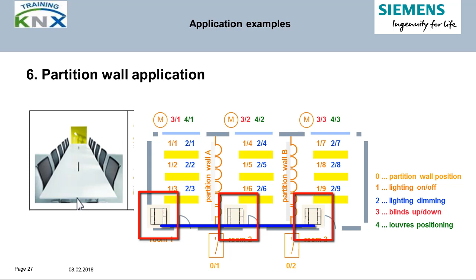The basic requirement is that several smaller, identical rooms shall be combined to bigger rooms, or even all of them to one large room by removing the partition walls. When this happens, all controls shall be paralleled, and that shall happen automatically, without the need of any manual reconfiguration by computer or even rewiring. This is possible with KNX and special controllers because of the strict separation between sensor and actuator functions.